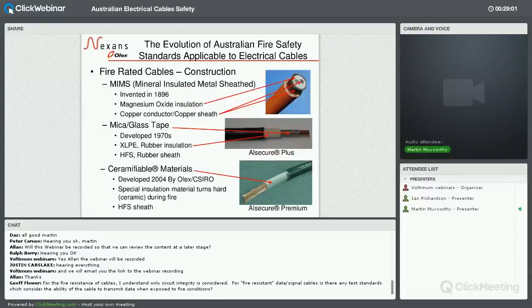It wasn't until much later on in the mid-1900s that people learnt of its value in fire or circuit integrity type applications. Magnesium oxide insulation makes it a very high temperature rating, and of course the copper conductor and the copper sheath enable it to also operate at extremely high temperatures.